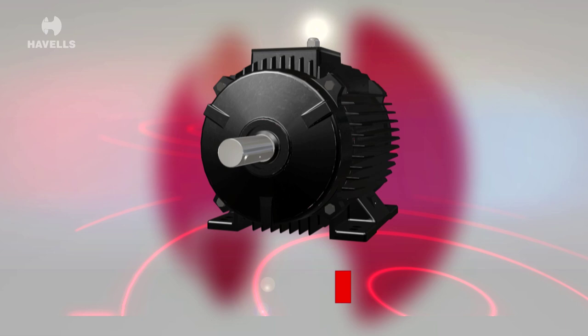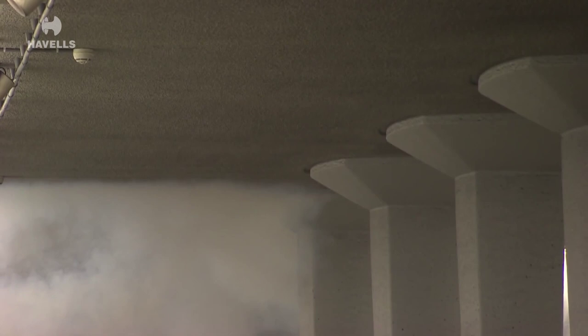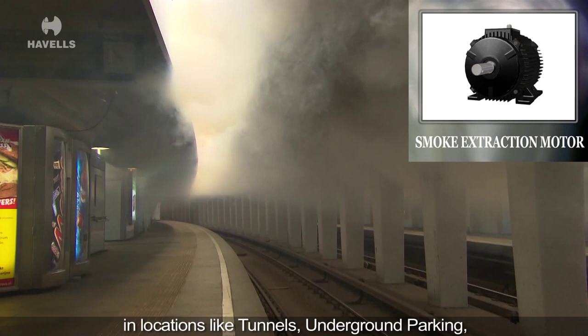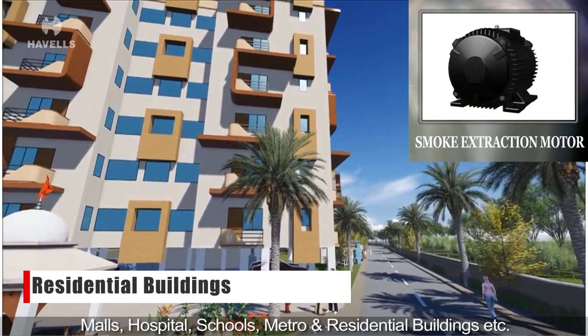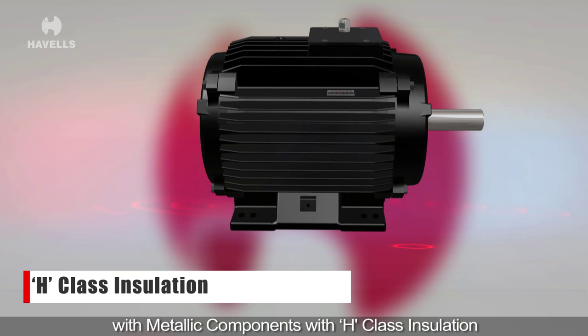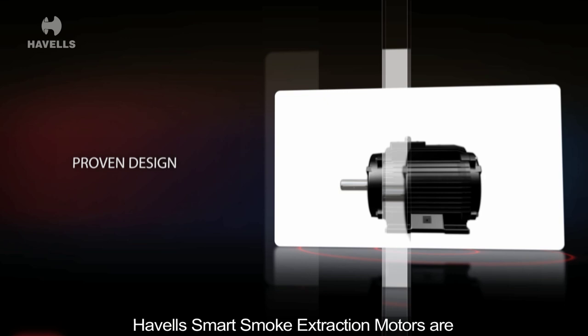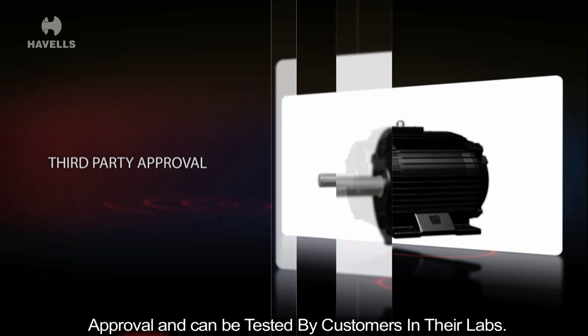The smoke extraction motors are totally enclosed motors adept to work under high temperatures up to 300 degrees Celsius to extract smoke from buildings in case of fire, in locations like tunnels, underground parking, malls, hospitals, schools, metro and residential buildings, for blower fans. Havells smart smoke extraction motors are built with metallic components with H class insulation and supplied with flying leads. These motors have a proven well-accepted design and help create a safe atmosphere by removing smoke in case of fire. They are painted with color RAL 9005, have third party approval and can be tested by customers in their labs.